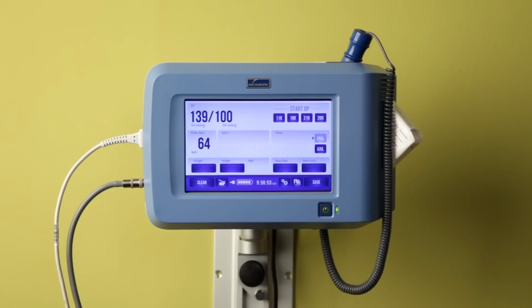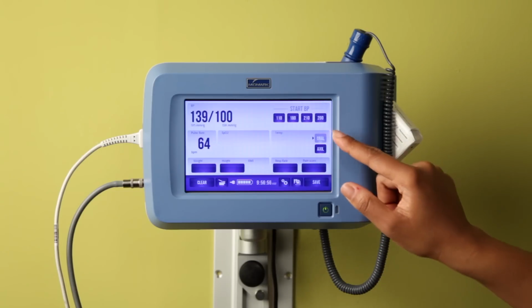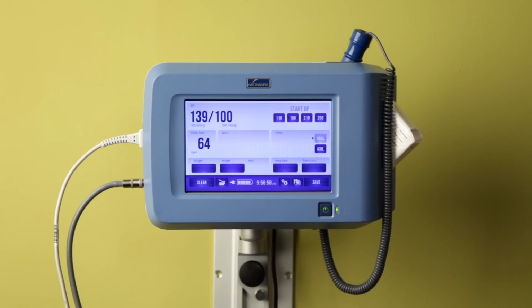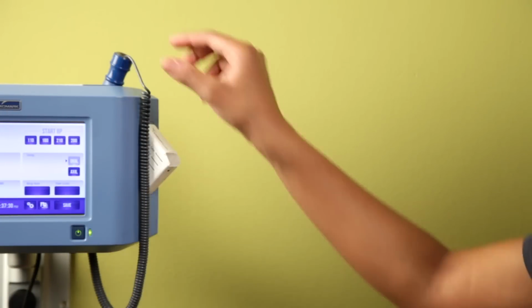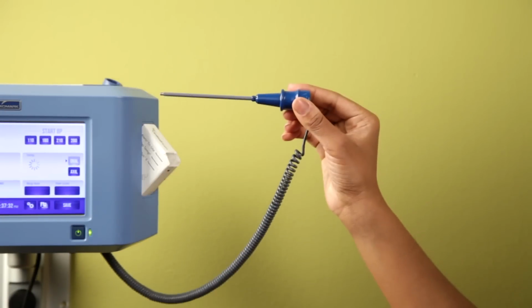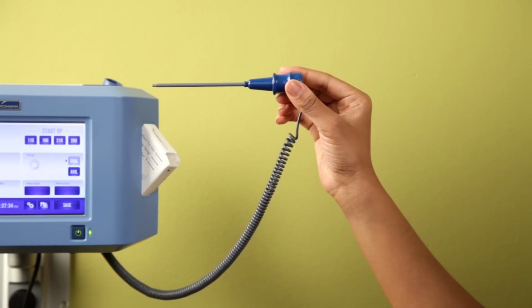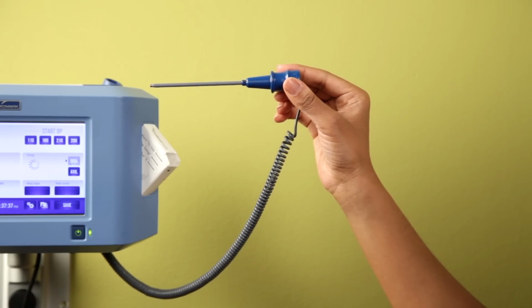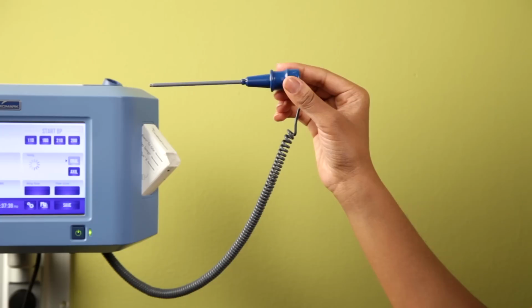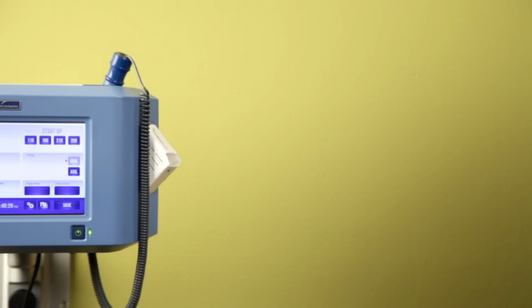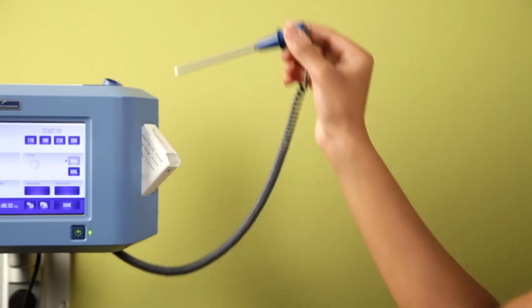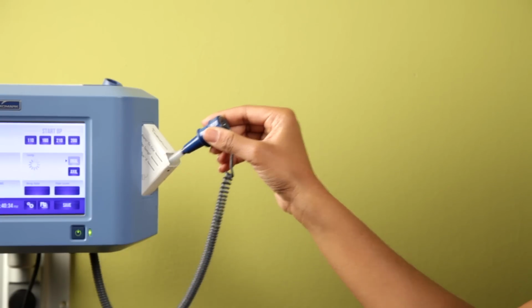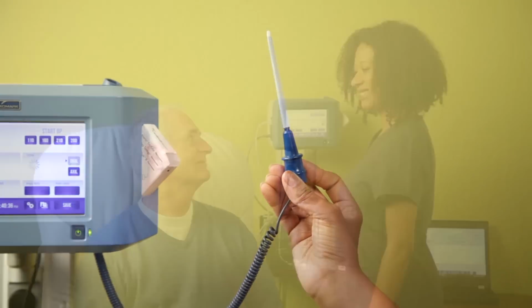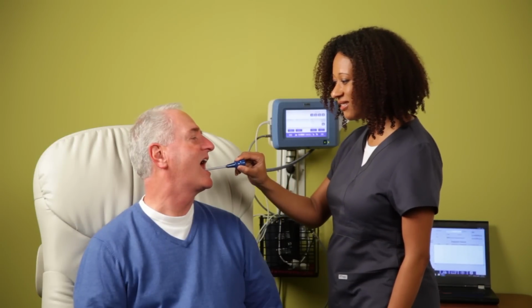To take a temperature, check the appropriate button in the main testing screen, oral for oral readings and axil for axillary readings, and make sure that the button is light blue. Remove the probe from the probe well, grasping it in the top blue area between the thumb and index finger. Do not press down on the area where the cord comes out of the top. An audible tone will sound when the probe has been removed from the storage well. Insert the probe in the probe cover and gently press down on the cover to ensure a secure fit. Place the probe in the appropriate location on the patient.